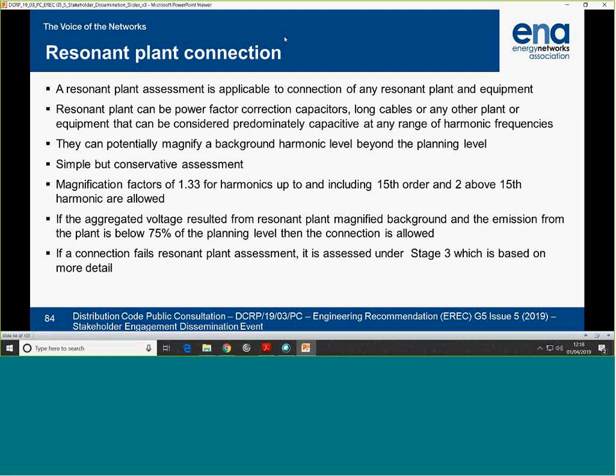Can you apply for that? I think you can apply for that information. Yeah, you have to pay for it. Okay. More information is going to come out eventually with the Open Networks projects that they're doing. This sort of information will start disseminating out. But if you're looking at trying to get a minimum 11 kV fault level, well, take out a transformer, N-1. The primaries are normally fed by two transformers, so you take one of those out, and there you go. But the maximum fault level is at the top, as well as the minimum fault level. Just understand that the LTDSs are there and you can use them. It's just how far you want to develop it up front. And you've got to use recognised software to model those things.